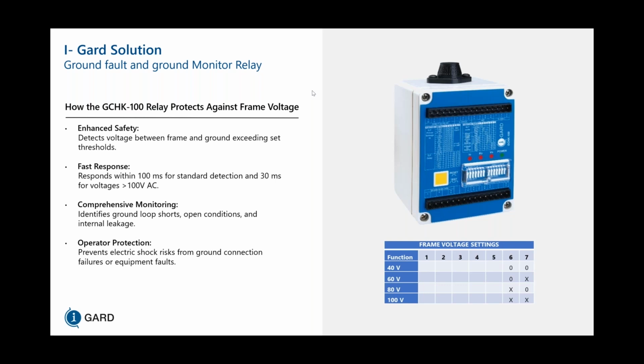Does this ground monitor relay work for high voltage substations too? You can potentially use it on trailing cable as well, but we also do sell ground fault monitors by themselves without the ground check feature if needed, and that's where you can use the Sentry relay, which has a trip range between 0.5 amp to 1200 amps and tripping within a second or less to meet those requirements of ground fault only. If ground fault ground check is needed at high voltage, then the GCHK 100 doesn't have voltage limitation.